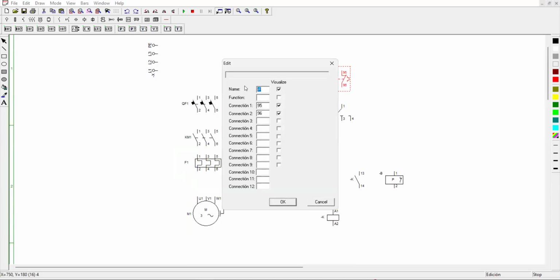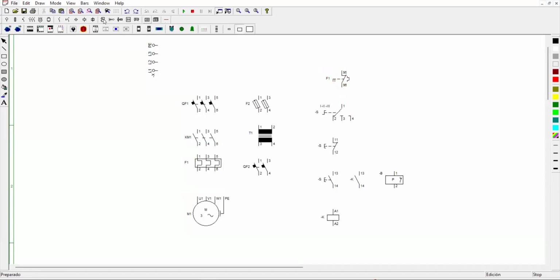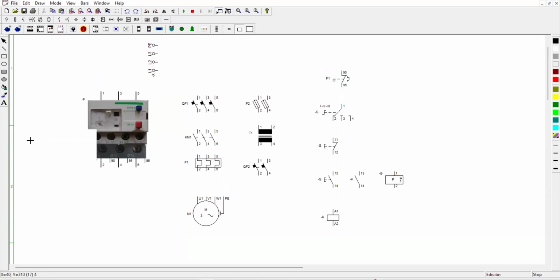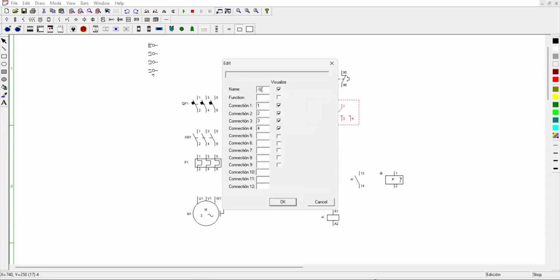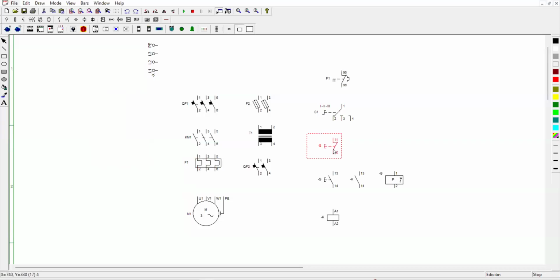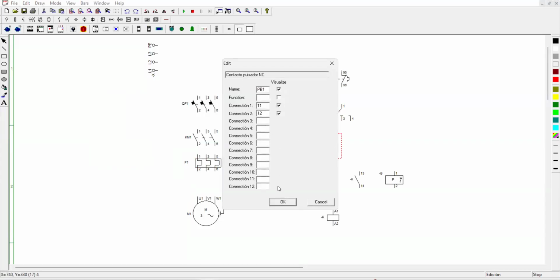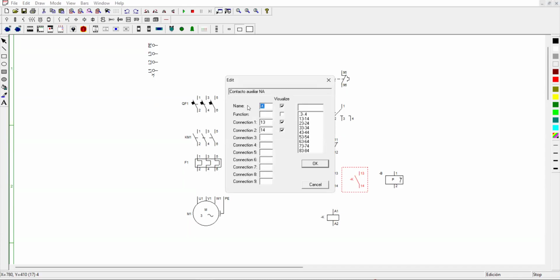Then this will be our thermal overload F1, 95 and 96. This is referring to this overload relay. This is a thermal overload of a magnetic contactor by Schneider Electric brand. Of course, this will be our selector switch S1. I will use this as push button 1, PB1. Stop push button, so this will be our PB2, the start push button. Then this will be our auxiliary contact of magnetic contactor KM1.